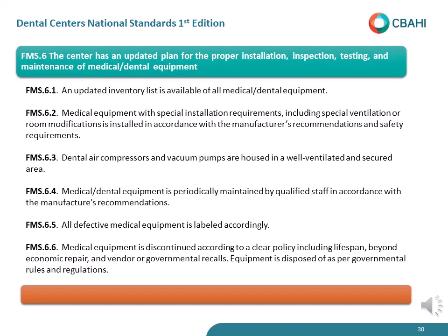6.5, all defective medical equipment is labeled accordingly. So a requirement here: if you have any malfunctioning or defective equipment, it needs to be tagged. So the next staff, when they see it, they know about it. We don't want it reused on a different patient when it has a defective operation.